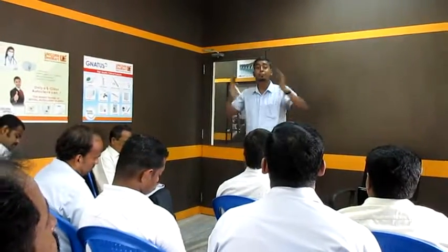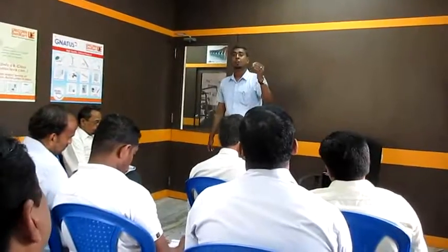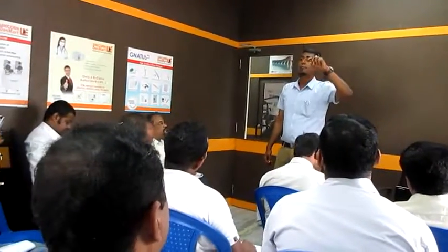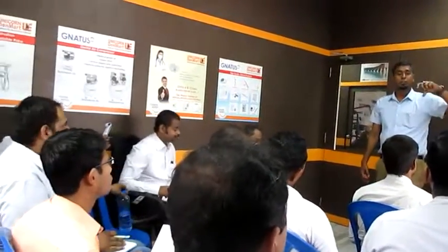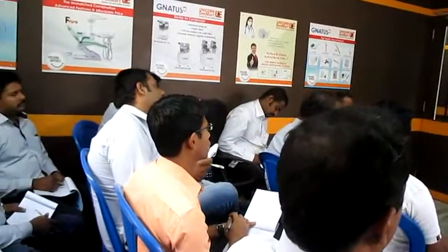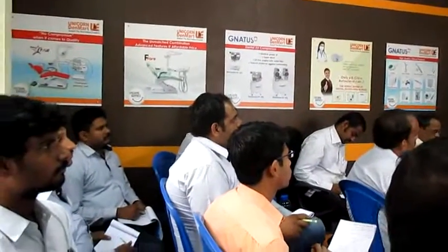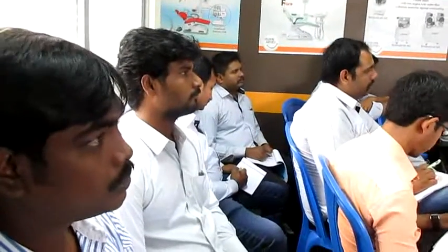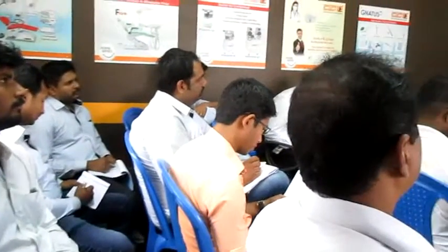That's why the manufacturer doesn't manufacture a very small focal spot, and doesn't manufacture a very big one. They made it intermediate, neither big nor small. Because of cooling, a smaller focal spot will have more cooling time, and a bigger focal spot will have less cooling time. We want lesser cooling time also, right? This is the role of the focal spot. Got it? Any query for the focal spot?